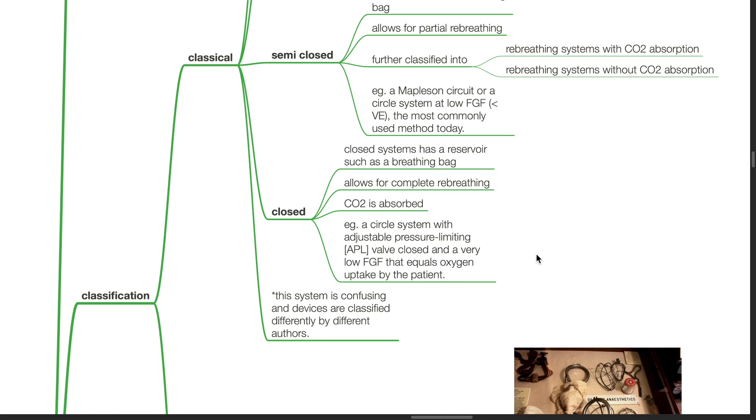Closed systems has a reservoir such as a breathing bag and allows for complete re-breathing. CO2 is absorbed. For example, a circle system with APL valve closed and a very low fresh gas flow that equals oxygen uptake by the patient.